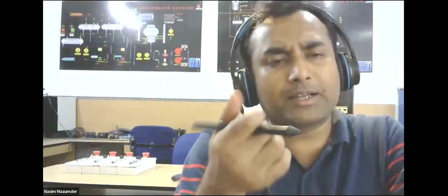you will be able to put the PLC or DCS in run mode so it will control the whole process. Now, while programming this PLC or DCS CPU, we have to configure what types of modules are there, what type of inputs or outputs are there. Each and every channel we have to configure, otherwise the PLC will not be able to identify what device has been connected to it on that particular channel.